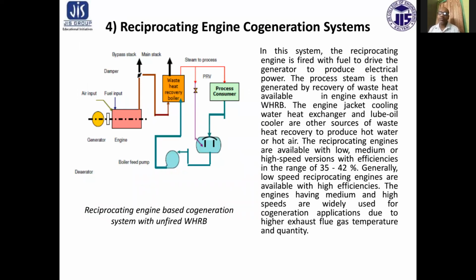Number 4, reciprocating engine cogeneration system. In this system, the reciprocating engine is fired with fuel to drive the generator to produce electrical power. The process steam is then generated by recovery of waste heat available in the engine exhaust in a waste heat recovery boiler. The engine jackets, cooling water heat exchanger, and lube oil cooler are other sources of waste heat recovery to produce hot water or hot air.